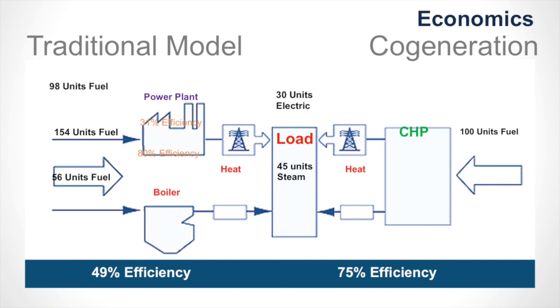So in cogeneration, for a site like a college or a hospital where you constantly have a need for heat - because of dormitories, showers, hot water, cooking - if you create your own electricity, you can use that heat. You're not going to throw it away like the utility. So that's what we do. Here we take that same 100 units of fuel in, we're serving the same load, but we now have 75% efficiency because we're not throwing any of this away while making this. This is 50% more efficient than that. Since we buy fuel at the same price - the price of natural gas is the price of natural gas, whether PP&L is buying it or me - if I can get a much higher efficiency, I have a much lower cost.